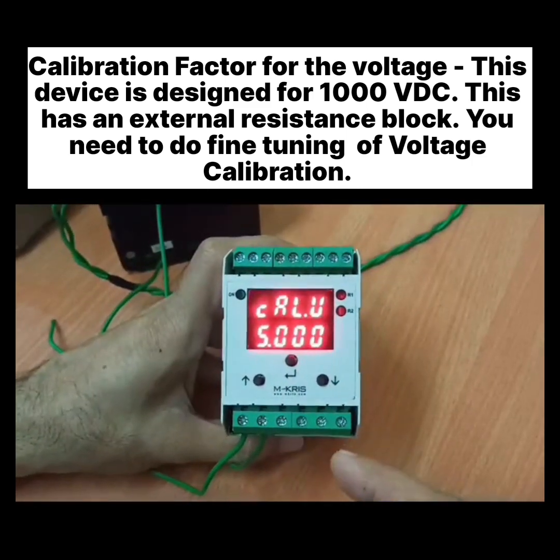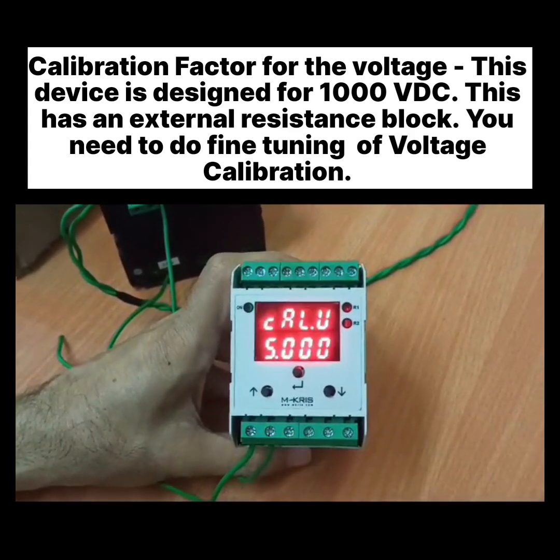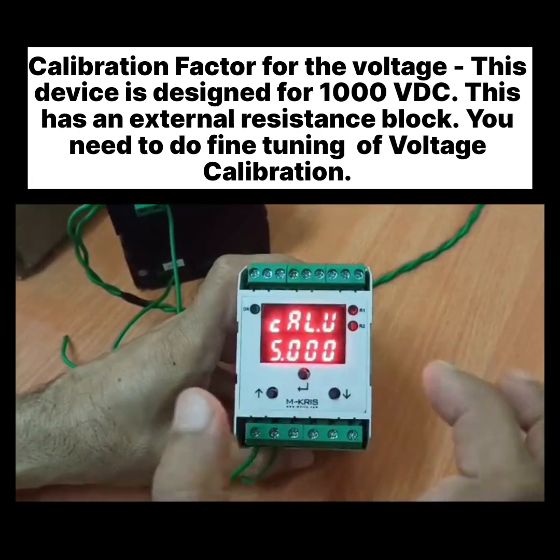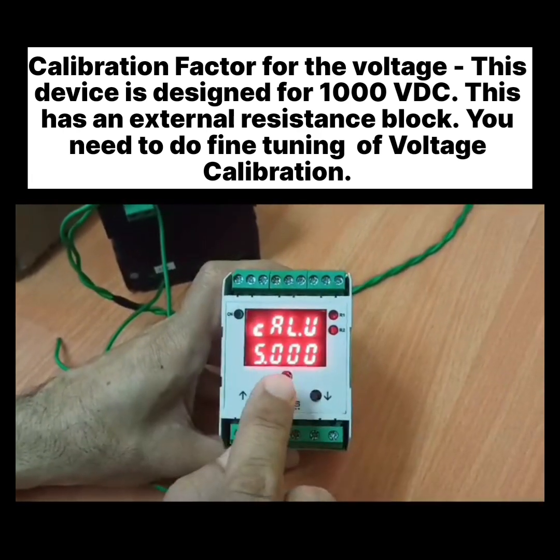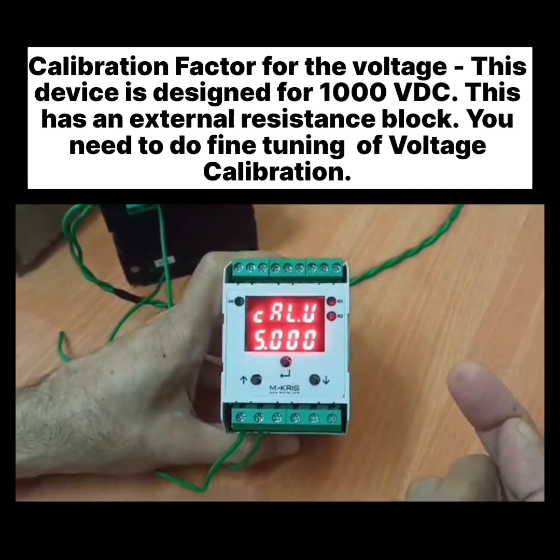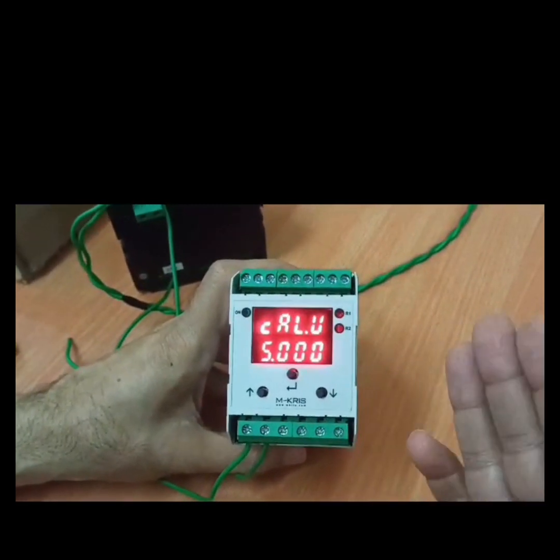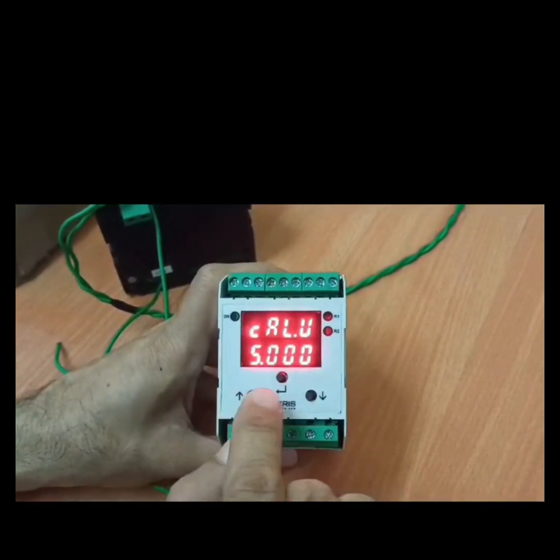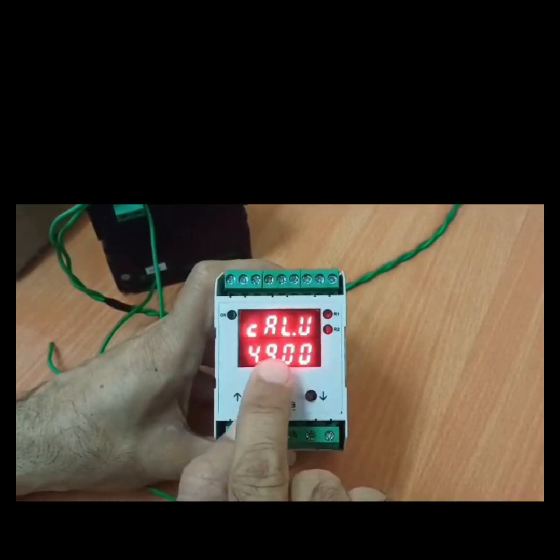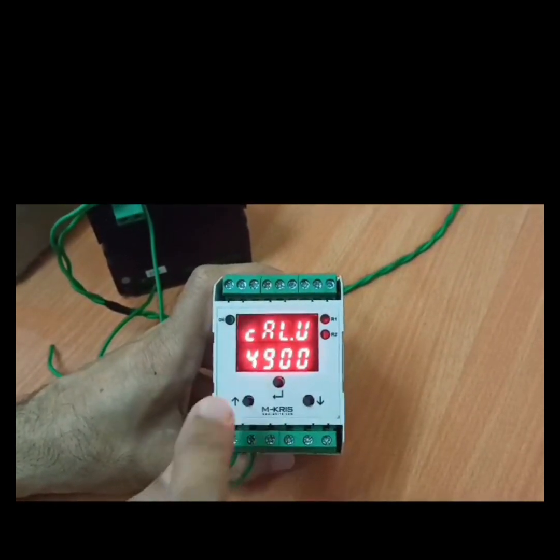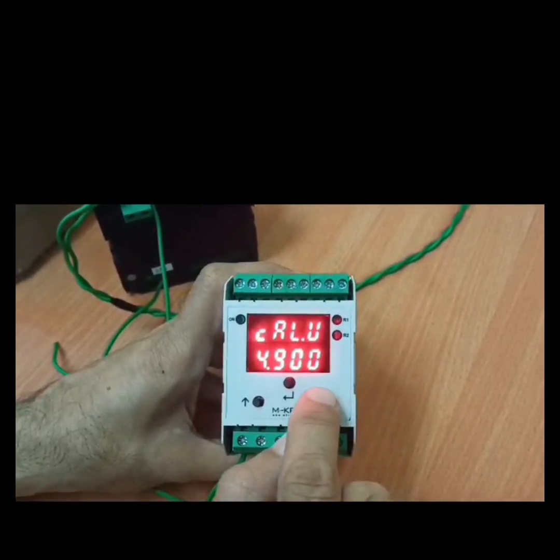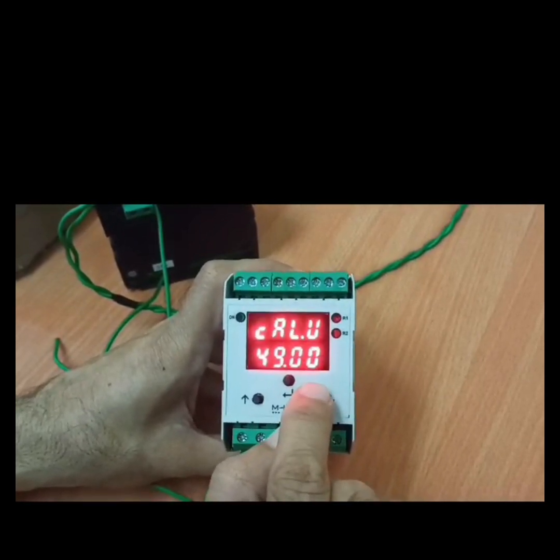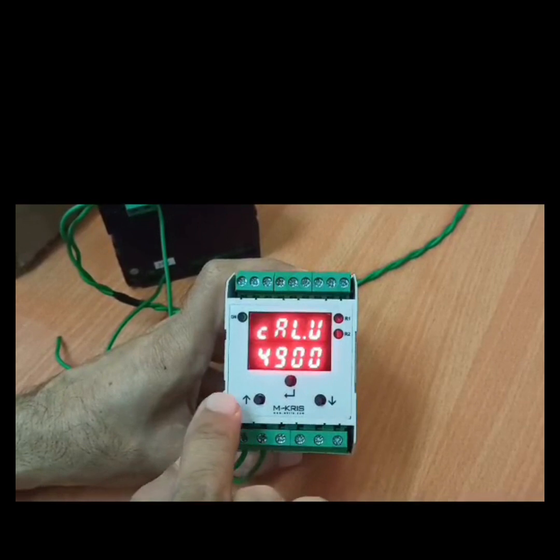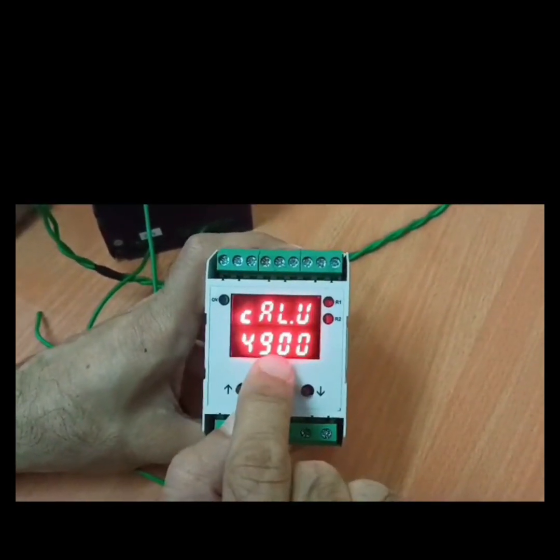The next parameter is the calibration factor for the voltage. As this device is meant for 1000 volt DC, it has an external resistance block. You may need to do some fine tuning of the voltage calibration, as presently it is done for 5. So if, let's say, the multiplication factor comes to be about 4.9, you can change it by pressing this button again, reducing it to 4. This can be reduced to 9, so this is now 4.9. Here even the decimal digit is floating, so you can change the decimal position. As we want to set it at 4.9, we will press the button.